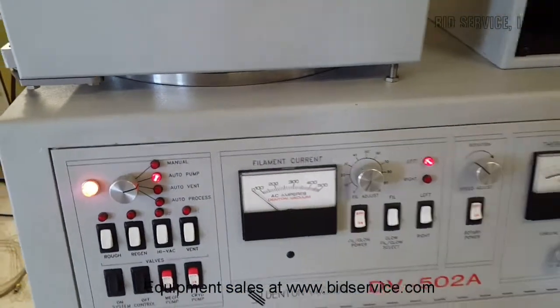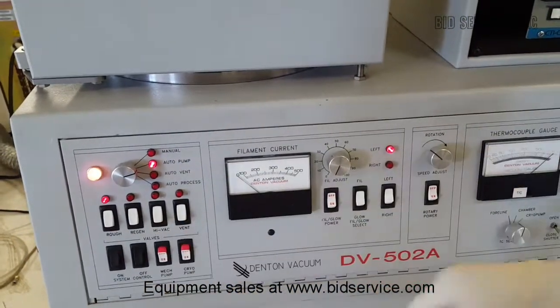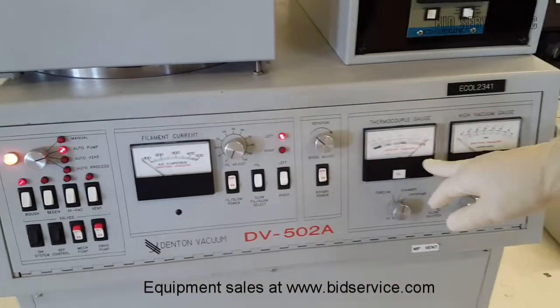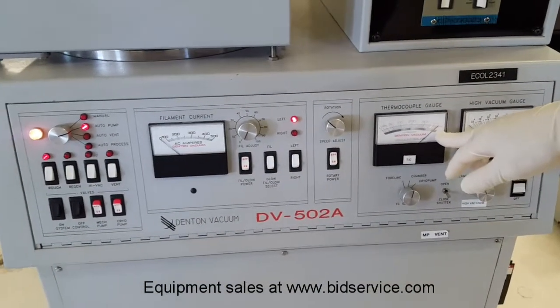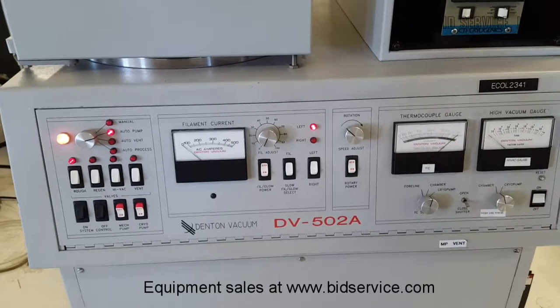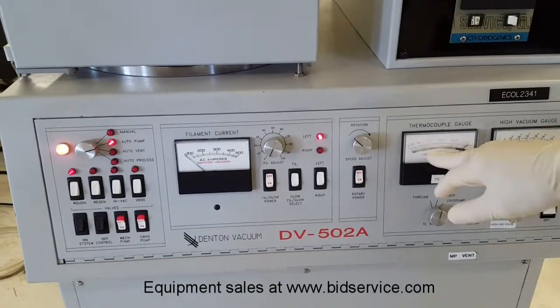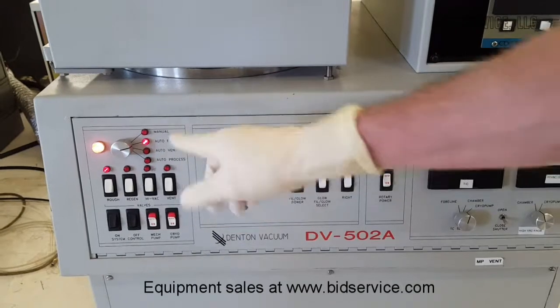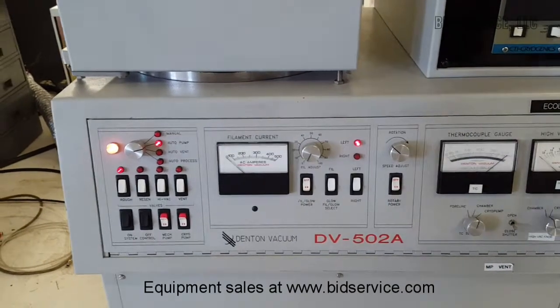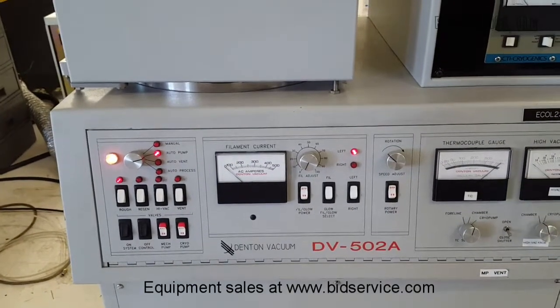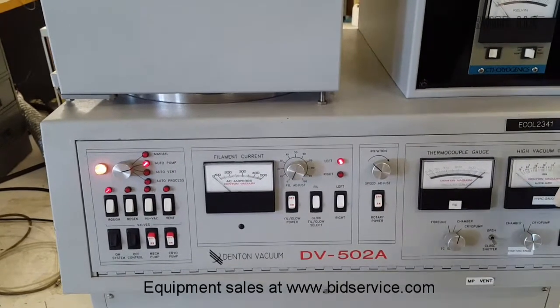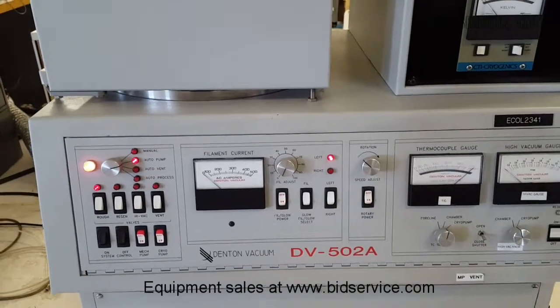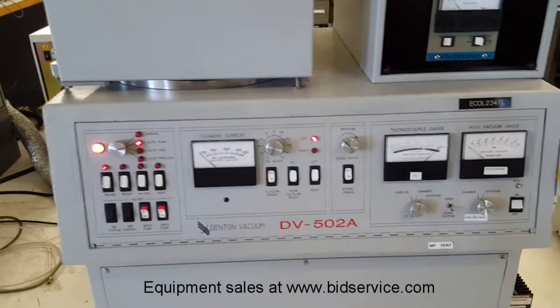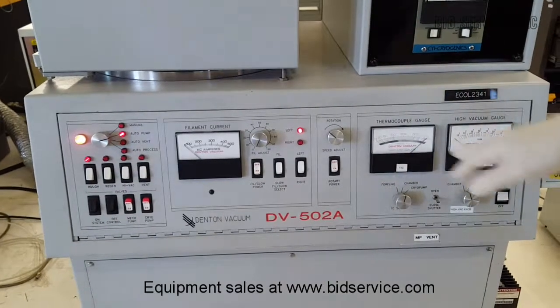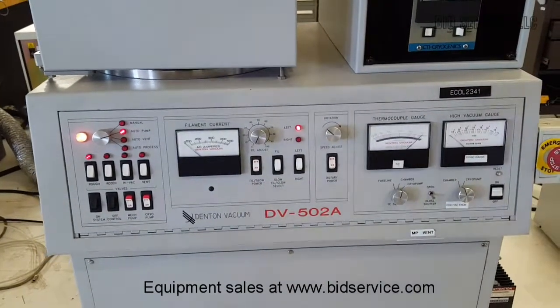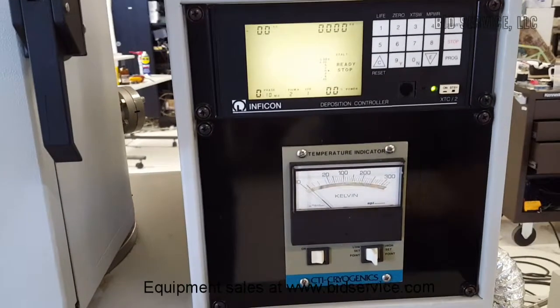And what this will do is you're going to see that the rough valve opens. There it goes now. It's going to start bringing down the chamber vacuum. There's an automatic crossover here, so once it hits that 150 millitorr, it'll cross over and open the high vac valve, and then turn the chamber cold cathode gauge on. And we'll get a reading here with the high vac gauge reading. This will take a few minutes, so we'll come back once it gets close to the crossover. Waiting for the chamber to pump out.